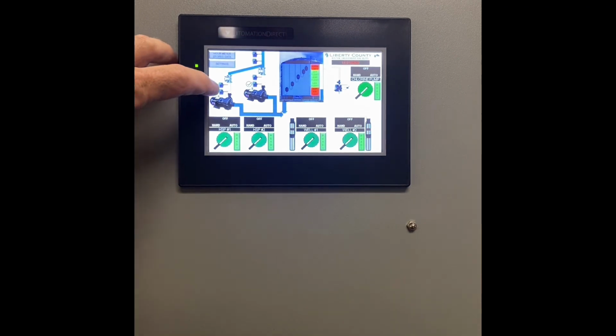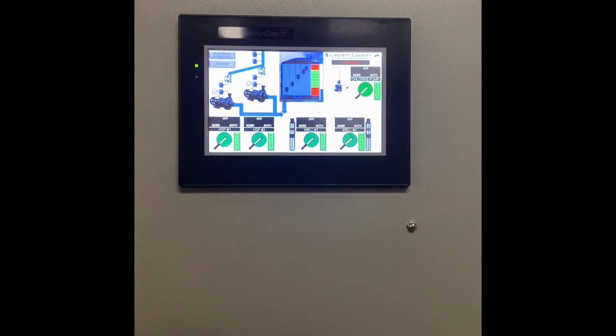Now, up above the high service pumps, you'll notice that we have an empty section of pipe. When our feedback from the soft starts for those 2 pumps is in the high state or on state, then that respective section of pipe will illuminate blue to let you know that the system is indeed seeing feedback from that motor saying that the soft start is in the full run mode. If it does not receive that feedback signal within the allotted time per the setting screen, it will also cause a failure. Both pumps are identical in that control algorithm.